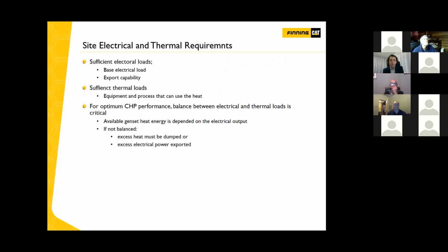Site electrical and thermal requirements are the main requirements for a CHP project—sufficient electrical and thermal loads, and base electrical loads. A steady-state constant load is required to justify the genset selection, and sufficient thermal loads are needed to properly utilize the heat source from the engine. The optimum system has thermal and electrical load balanced, since the available heat energy depends on the electrical output. Basically, how much we load the engine determines how much heat we're going to have.